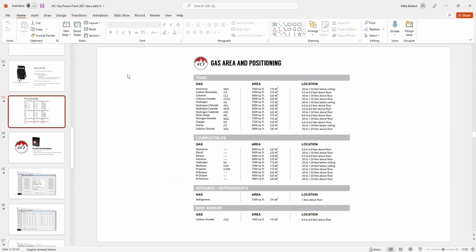Okay, I'll keep moving. Here's a sheet to give you an idea of where the sensor should be located in reference to above finished floor or below the ceiling. There are many more than this, but this is a good representation of gases and where they should go, and the square foot of coverage too. Like CO and NO2 are 50 foot in radius. We can get that information to you if you need it, but square footage is pretty standard across the board. These are just some of the typical ones. All right, before I move into the programming of the software, which is included on every job, any questions so far on the products themselves?